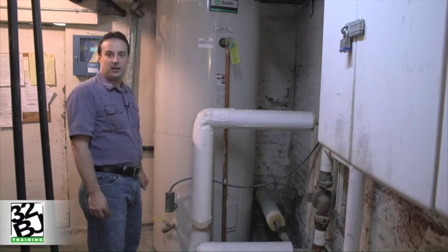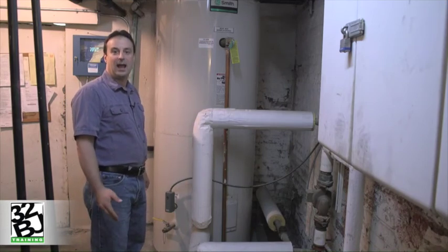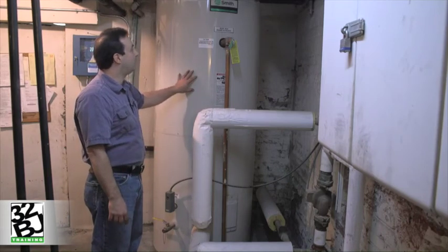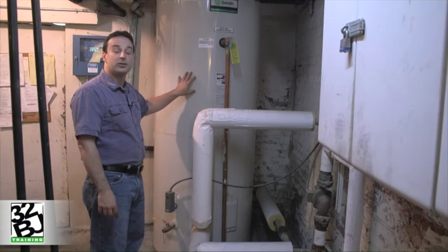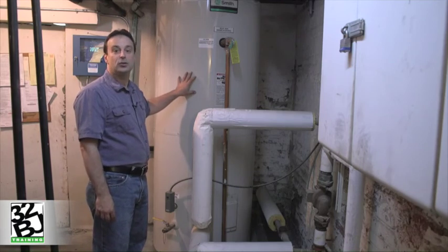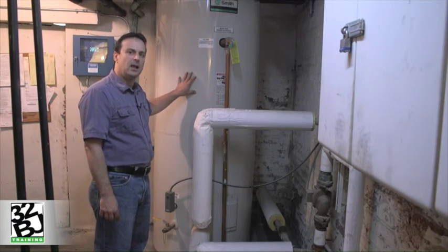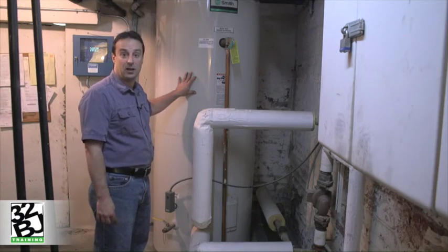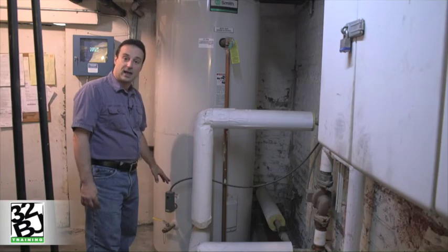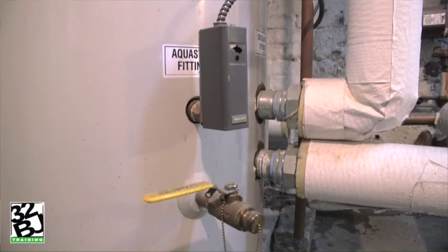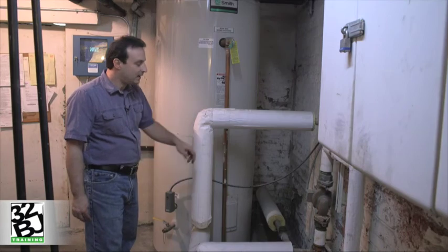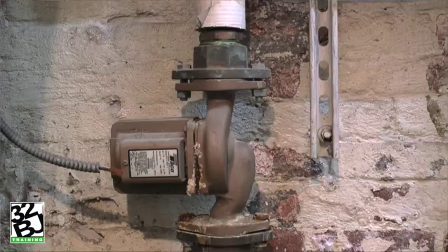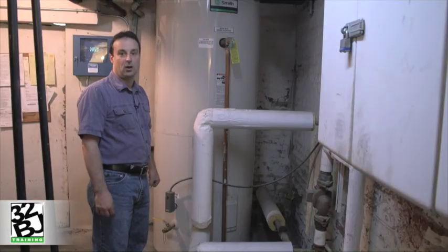After the water has been heated to 120 degrees Fahrenheit at the domestic hot water heater, it is circulated over to this 180-gallon storage tank. Because no combustion is taking place here, this storage tank can be heavily insulated to help offset some of those jacket losses that we saw with the hot water heater itself. It has its own aquastat, and when the water temperature drops below 120 degrees, this aquastat initiates the operation of a small pump which pumps that water over to the hot water heater to be reheated back to 120 degrees.